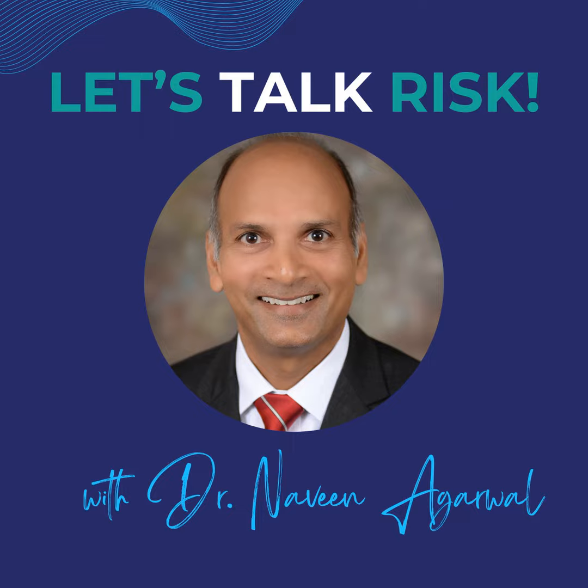Simulated use typically is one-time use when you talk about standard formative human factors or summative human factors testing. That's actually one of, in my opinion, the weaknesses of it. But I think clinical studies could provide a good opportunity to continue to monitor for that.